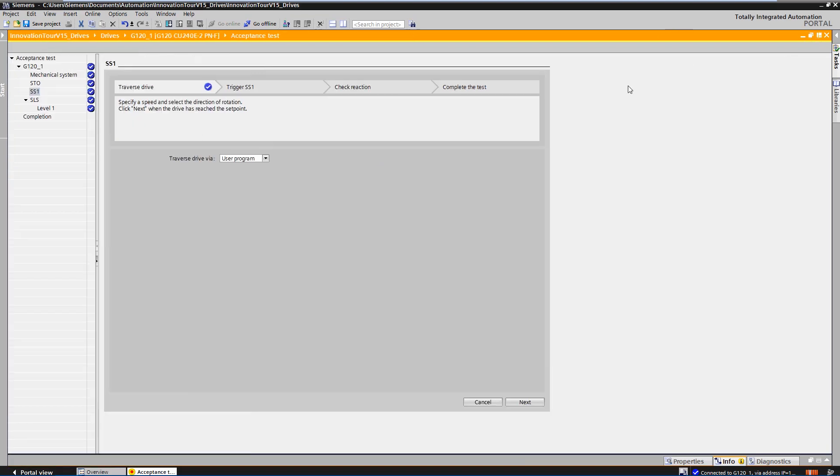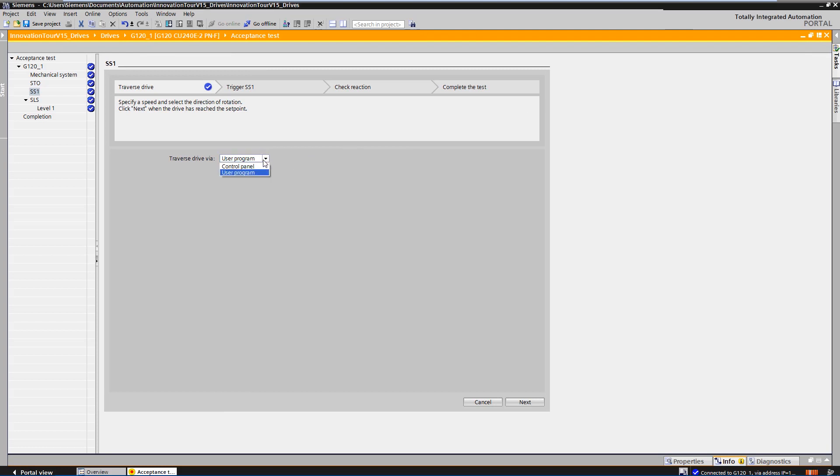Above, you can see the workflow through which you are guided step by step through the acceptance procedure. All steps include instructions on what actions the operator must perform and what drive behavior he must check. First, select how you want to move the drive. Via the control panel in the TIA portal or via the application program.